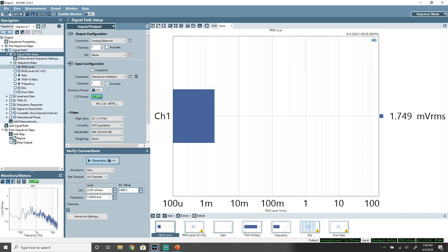Now I'm going to go ahead and click the box on input that says acoustic. Mainly what that is going to do for me is transform all of my input units from volts RMS to dB SPL, so that when I make my measurements, I can see them in the units of interest, which in an acoustic response measurement will of course be dB SPL. Next, I will check to make sure that my microphone connectors are correct on the APX 1701. In this case, I am using the unbalanced input for my reference microphone in channel number 1, and that is already there as the default.